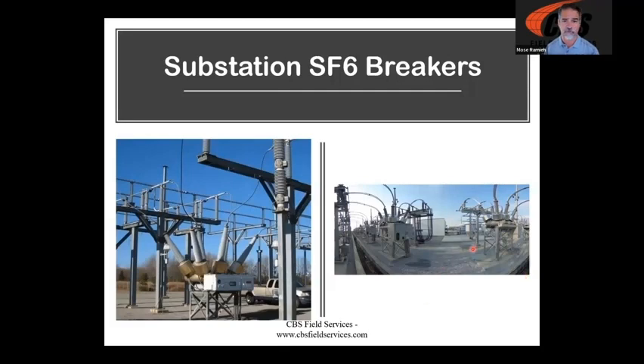Now, they come in a couple of different varieties. These are some substation types. This is a 161 class breaker over here, 35 kV breakers here. We're seeing gas insulated switchgear coming in there. We've got circuit switchers that are filled with SF6 gas. And as you're doing your routine inspections, please make sure that you check your gauges, that you're not leaking gas.